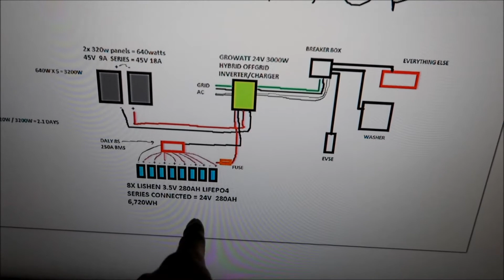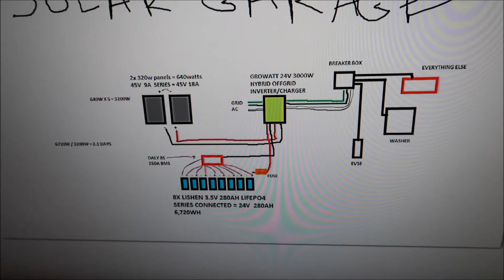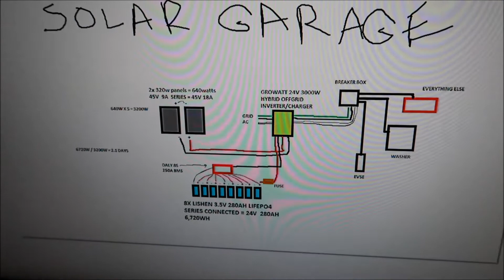If you multiply 280 amp hours times 24 volts, you get 6,720 watt hours - that's the battery bank capacity, almost pretty much 7 kilowatt hours of power.